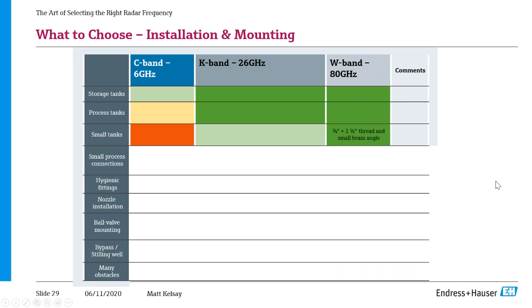In small tanks, low frequency is not recommended in very small tanks. High frequency will perform much better there in short ranges. It also doesn't hurt that high frequency has smaller process connections available, which leads right into the next one. As you increase your frequency, your process connections get smaller and smaller while being able to maintain the same type of beam angle and the same accuracy.